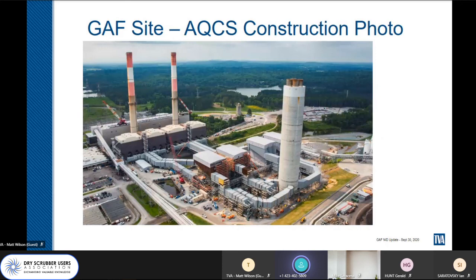Here is a terrific construction photo overview. On the far left is the powerhouse block itself. The brown and tan devices there, that look like buildings, are circa 1980 electrostatic precipitators. Those were the particulate pollution control devices prior to the startup of this new air quality control system. They were completely bypassed as part of this project, thus making the new air quality control system a full burden system, meaning all the fly ash generated from the boilers is carried over to the baghouse and dry scrubber, as well as the scrubber's byproduct itself. Thus, it's a full burden design.